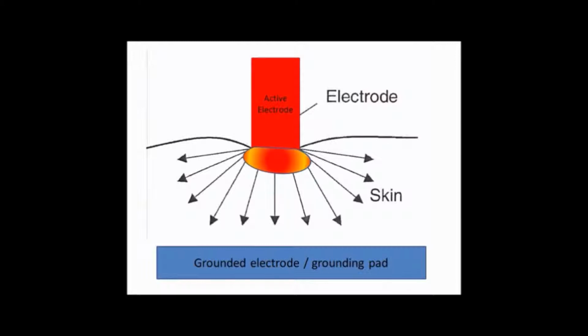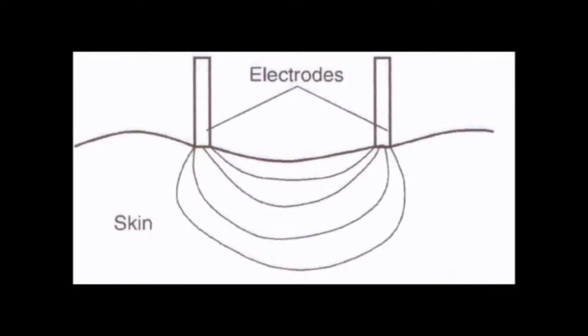The ability of the monopolar configuration to create a high power density on the surface of the electrode makes it popular in electrosurgery. However, the unpredictable behavior of a unipolar system as the current passes through the body to the grounding electrode is a disadvantage in aesthetic procedures since it may cause damage to the surrounding tissue, pain, and massive necrosis. Alternatively, the bipolar configuration uses controlled radio frequency, thereby reducing the chance of any damage to surrounding tissue.